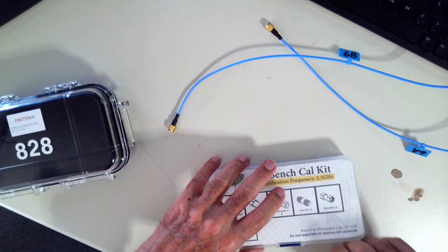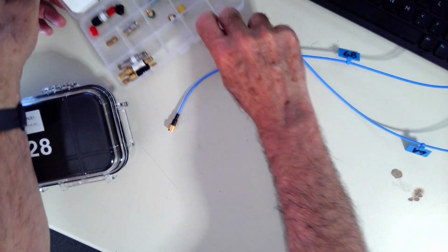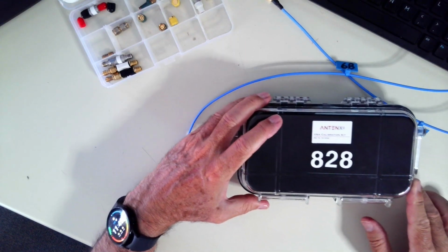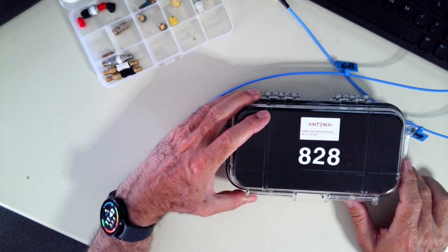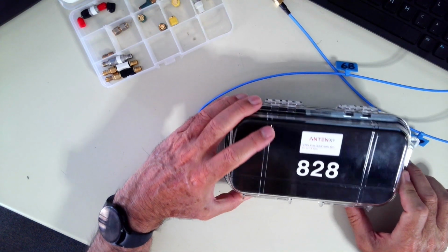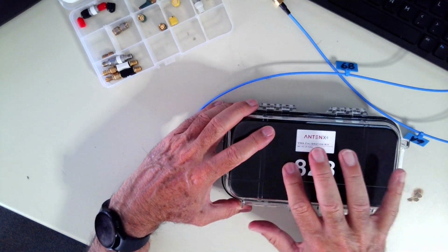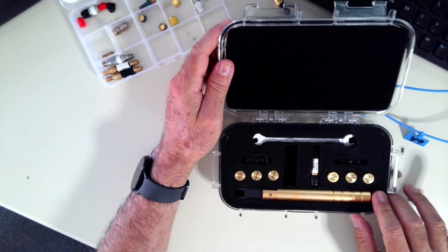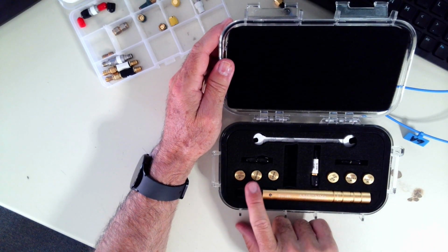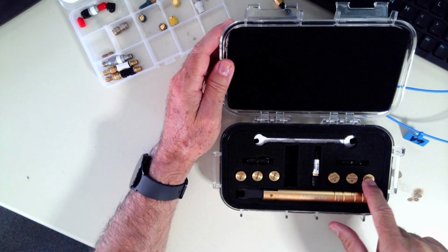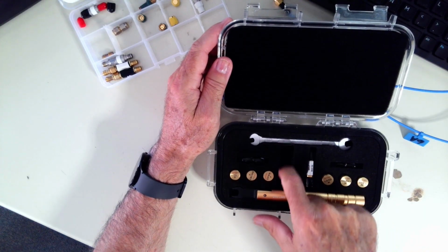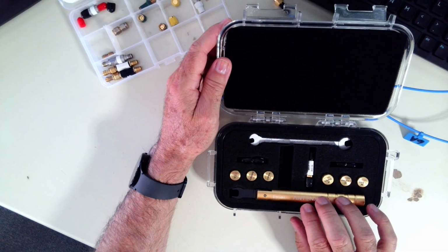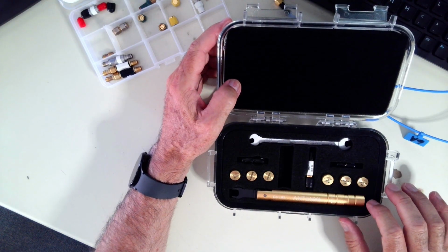We have another cal kit. Actually, we have several different cal kits here at the university for your use, depending upon what you're going to be working on. This one here is made by Antonex, and it is good to 15 gigahertz. This is a serial number on here because each kit that you buy from them is unique. They characterize their shorts, opens, and loads. This little open slot right here is where the thumb drive goes that had the data with it. I've saved that out of there so that it doesn't get lost.